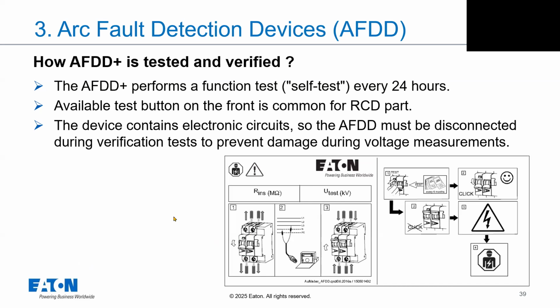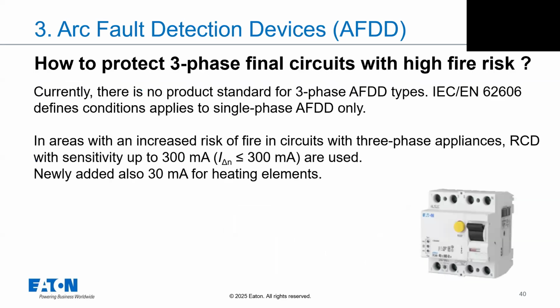One important topic, which is common for electronic devices: during verification of the installation with higher voltage measurement, it's necessary to disconnect the AFDD. It's the same case as, for example, SPDs. It doesn't make sense to measure an installation where there is an SPD, because it will not work. This test, then the same here. An electronic device must be tested in a proper way.